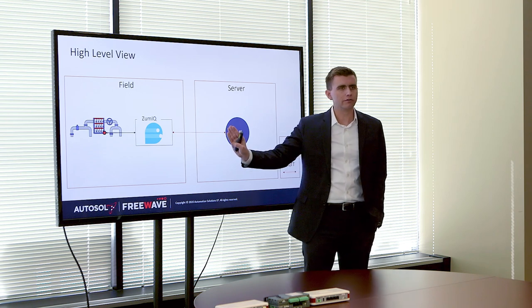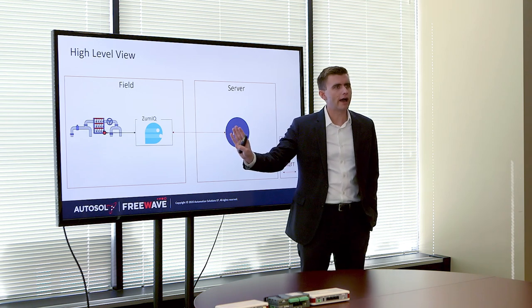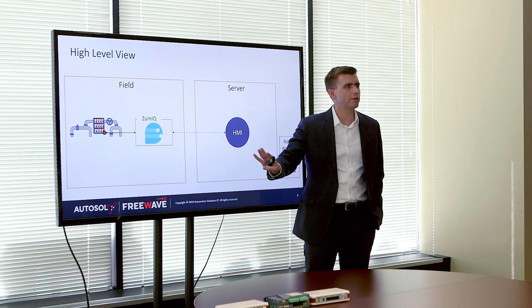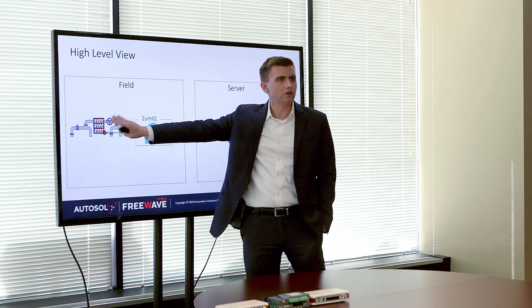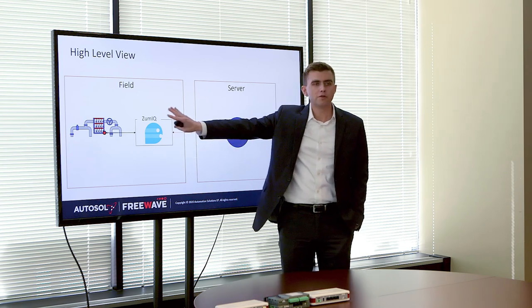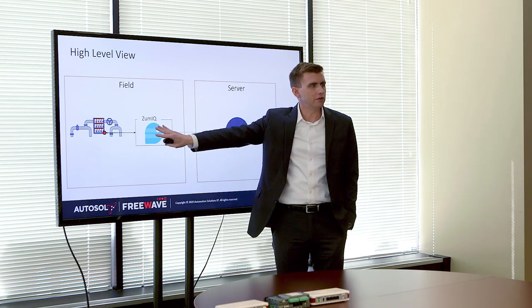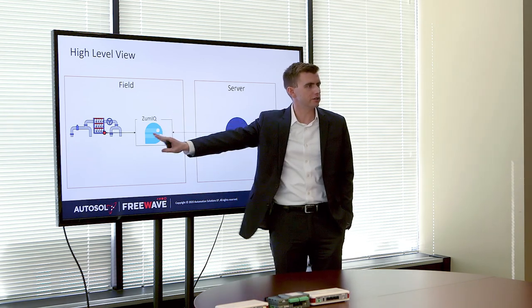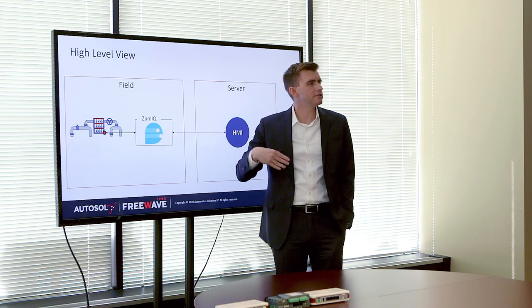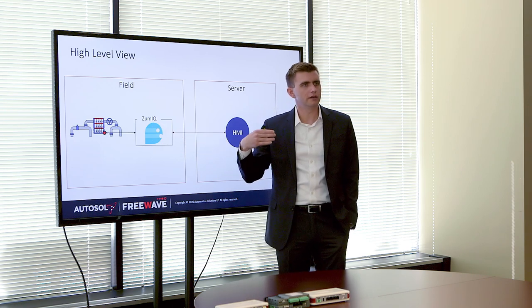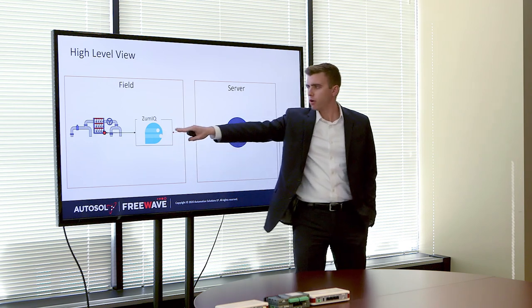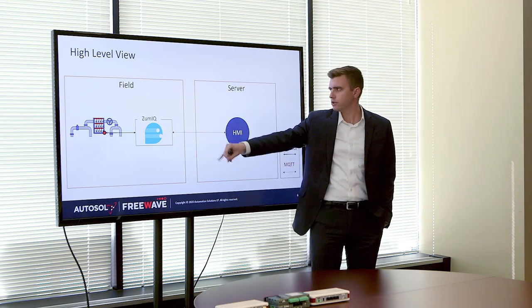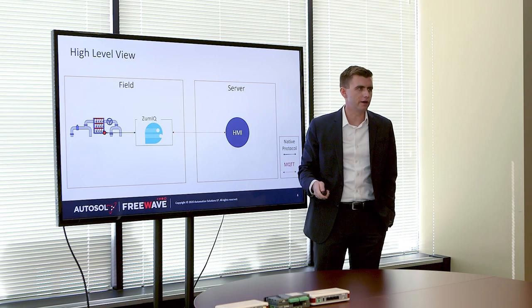Here's a very high-level overview of how Edge ACM and FreeWave fit into a SCADA model. You have your end device — total flow, ROC, Modbus, SCADApack — and then your ZumiQ deployed in the field with some communication connection to the end device. Edge ACM can talk to both serial and TCP-based end devices, pull that data in native protocol, convert to MQTT, and feed it back up to the server HMI.